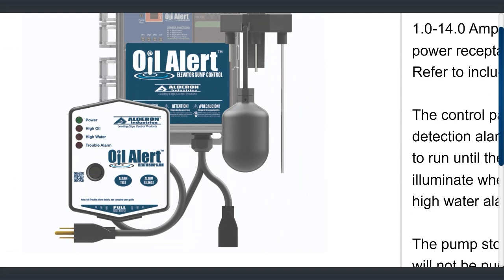If the probes are not contacting water, because oil is non-conductive and water is conductive. So we know that when it floats up and there's no continuity between the top probe and the other reference point, there would be an oil slick on the top. And if it's not, that means it's still water, so just keep pumping it out.